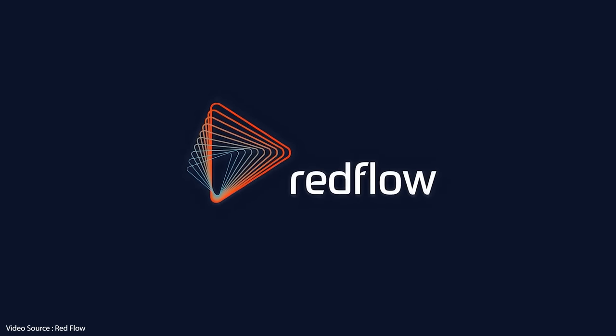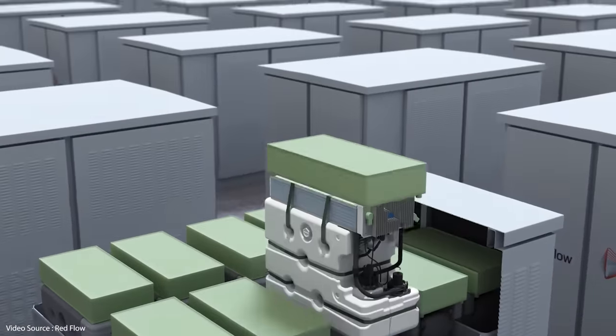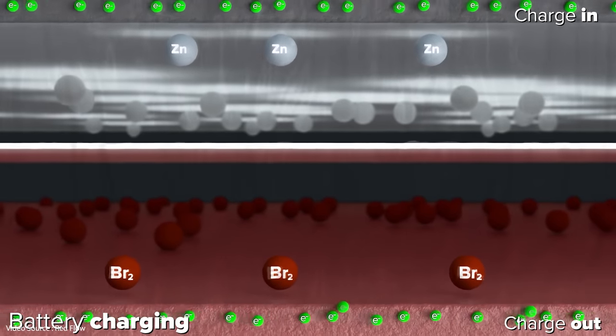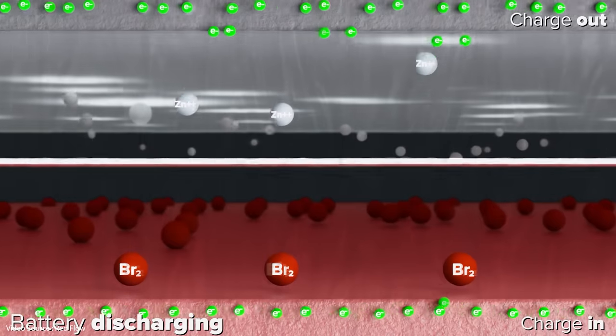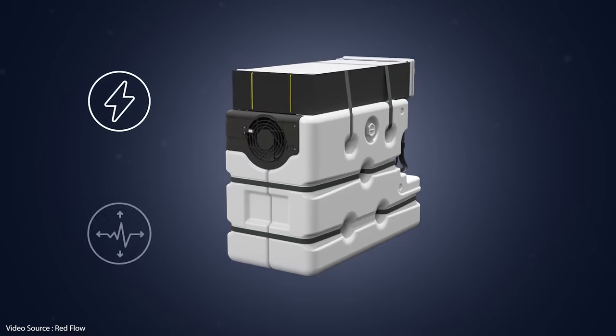And that brings us back around to Redflow, who I mentioned earlier. They come at the redox flow challenge from a slightly different angle. They still have two separate tanks containing solutions that get pumped across a stack of cells, but instead of using vanadium they use a zinc bromide solution. When the system is being charged up, the bromide gives up an electron in a process that converts it into bromine, which is then deposited on the electrode. Meanwhile the zinc ions on the other side gain a couple of electrons each and the resulting zinc metal gets plated out on the electrode on that side. During discharge the reaction is reversed. Because each zinc ion can capture two electrons at a time instead of just a single electron in a vanadium setup, you effectively get twice the bang for your buck — each of their 10 kilowatt hour modules only needs to be half the size of an equivalent version using vanadium tanks.